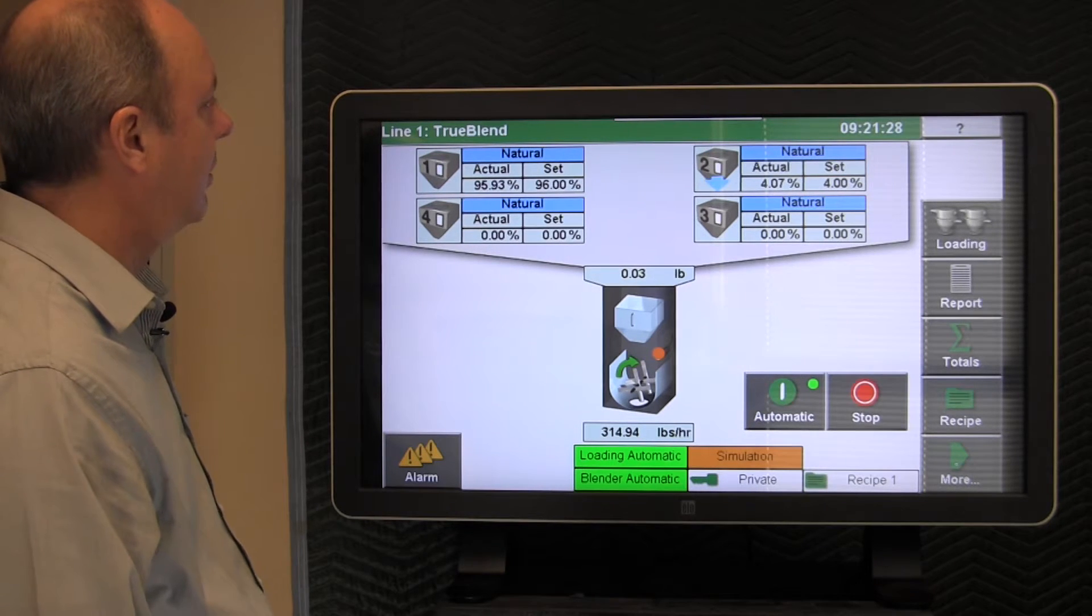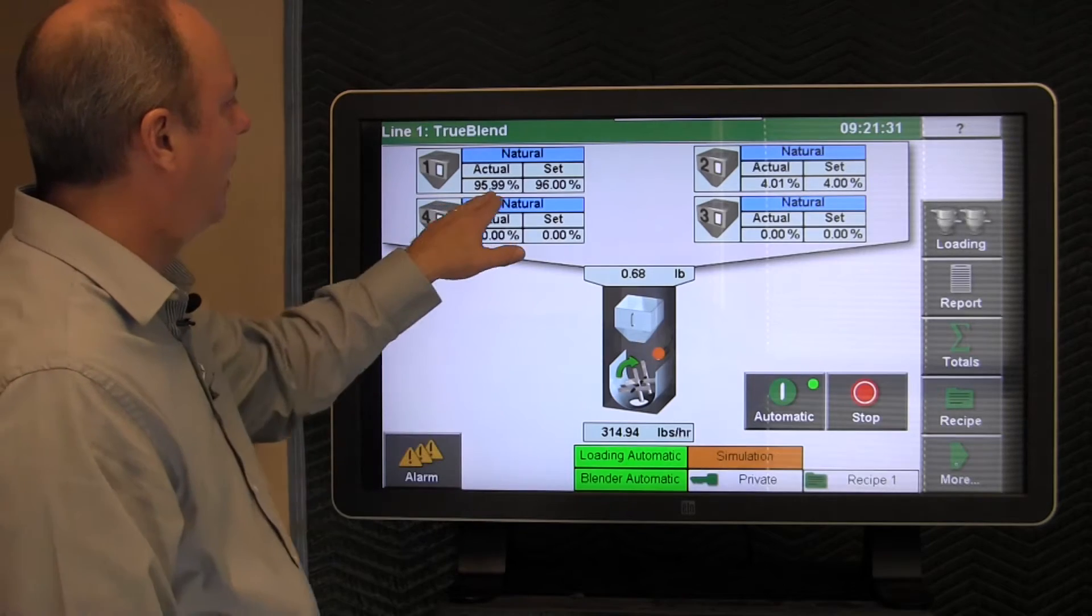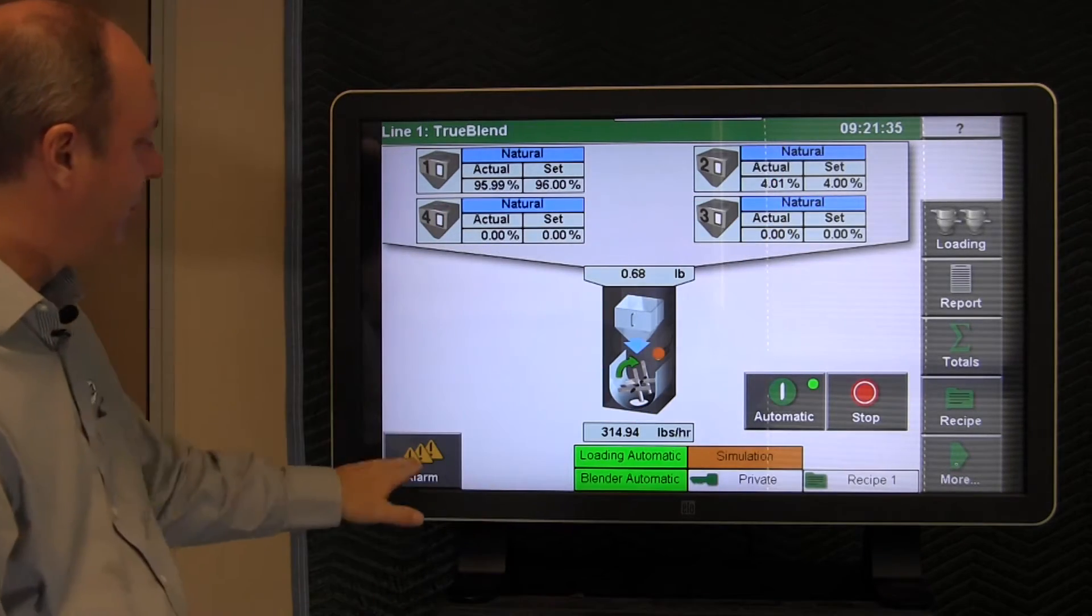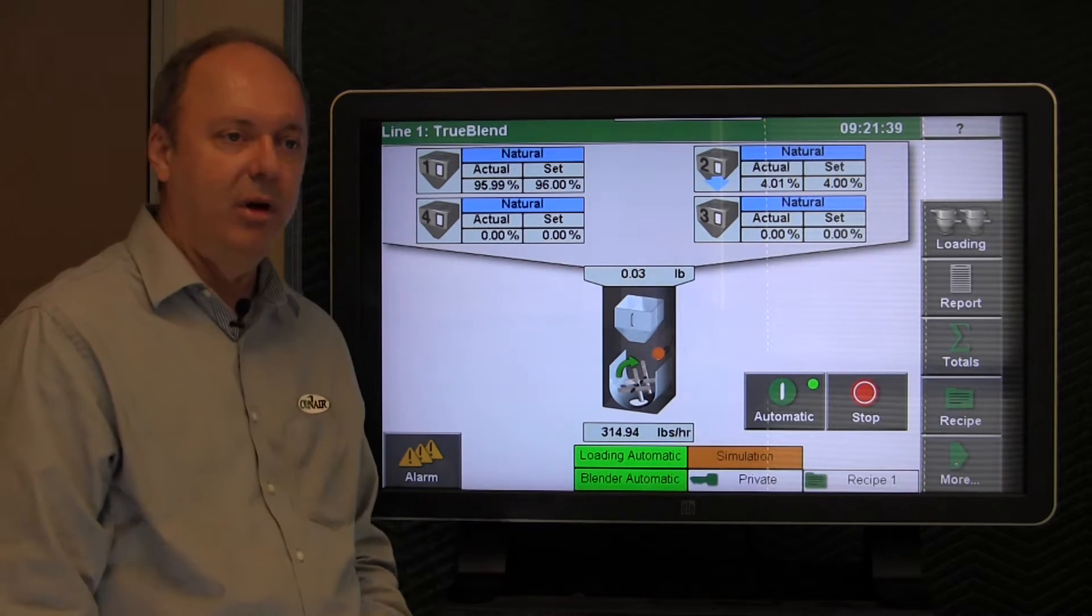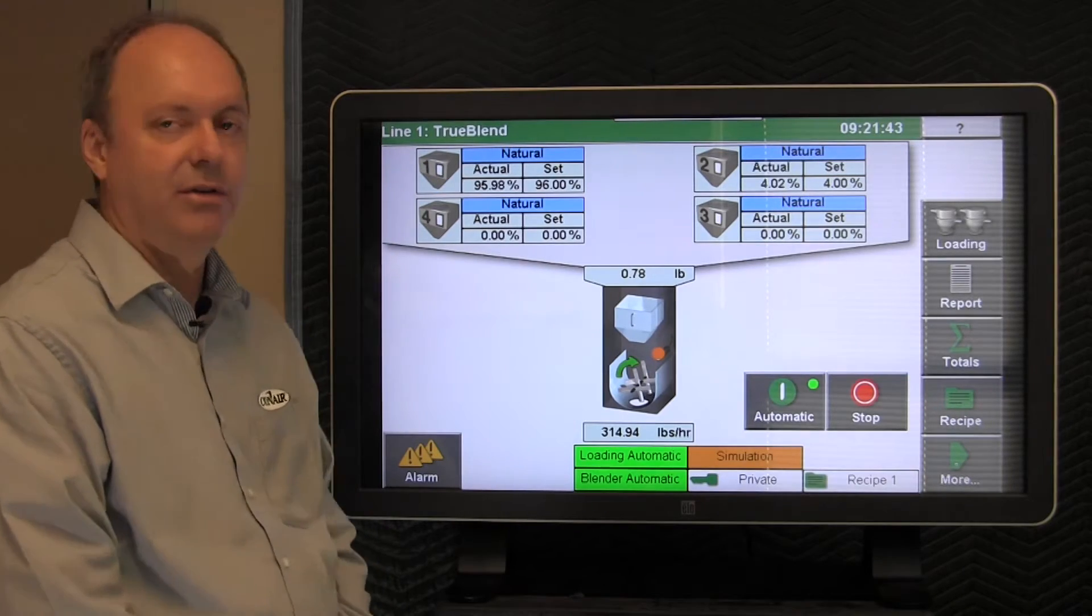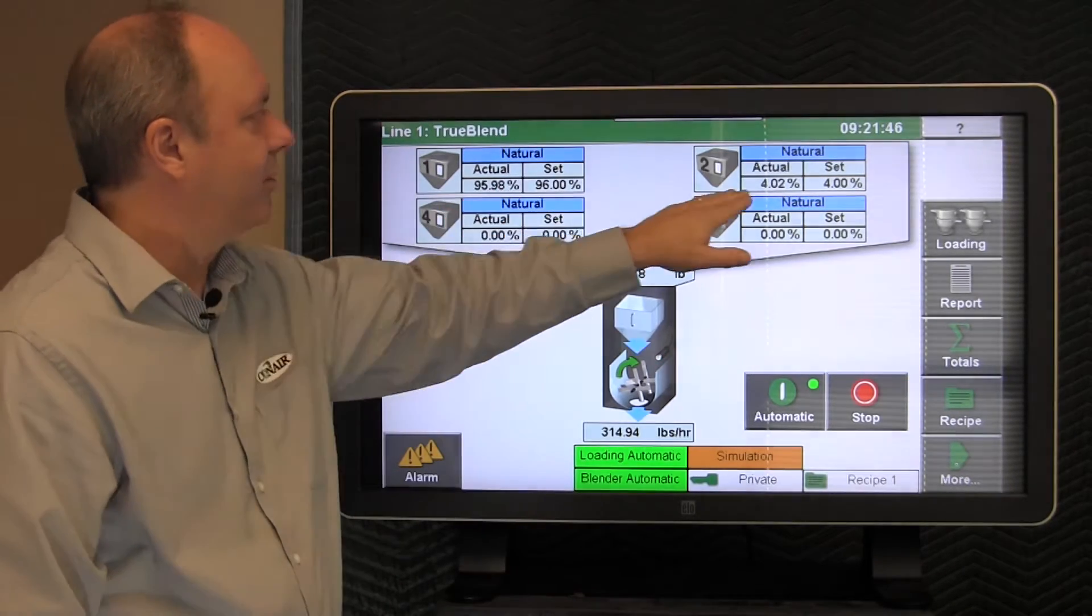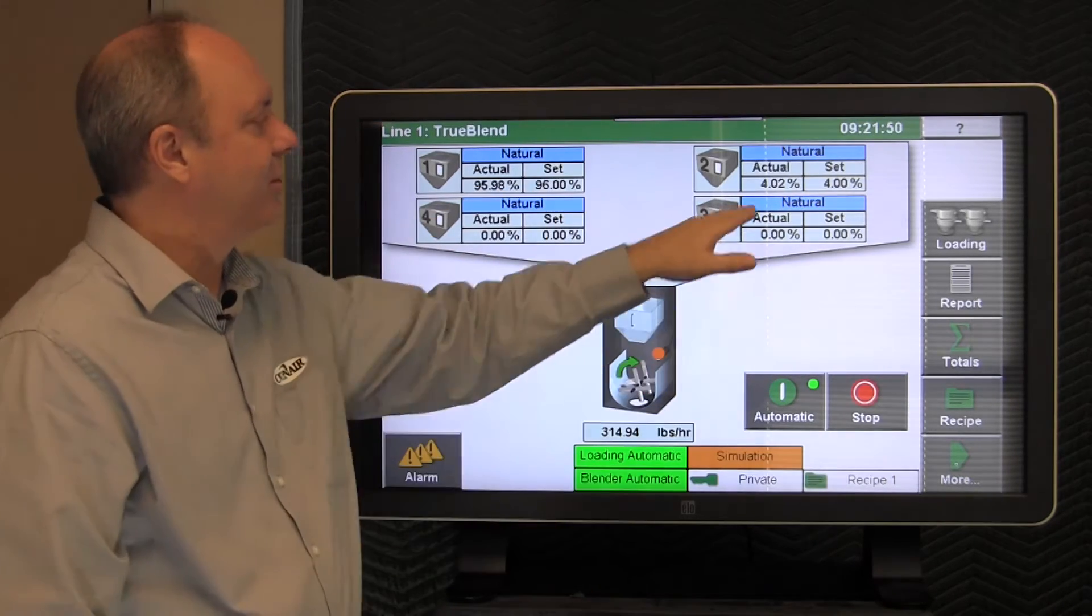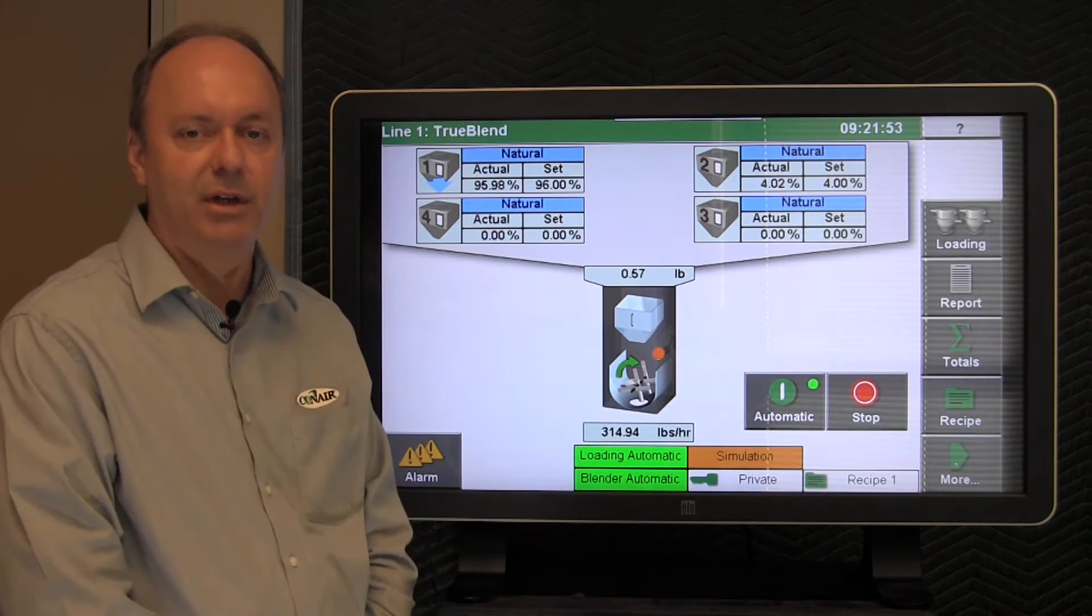So if you're running the blender, everything's running well, you have some good set versus actuals here, and you're alarm free. If you have an issue with the material flowing or you suspect it's not as accurate as it should be, that would be indicated here as well. The percentages would not be hitting. The actuals would not be lining up with the sets satisfactorily.